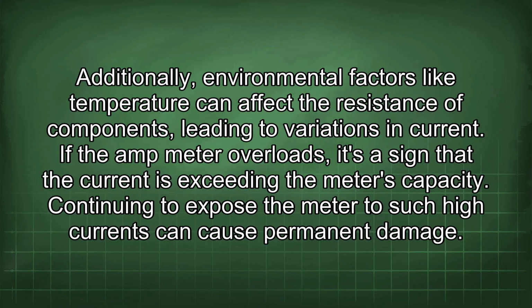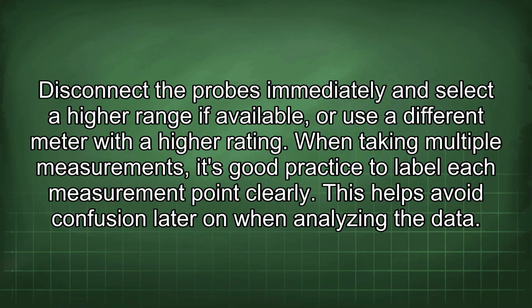If the amp meter overloads, it's a sign that the current is exceeding the meter's capacity. Continuing to expose the meter to such high currents can cause permanent damage. Disconnect the probes immediately and select a higher range if available, or use a different meter with a higher rating. When taking multiple measurements, it's good practice to label each measurement point clearly. This helps avoid confusion later on when analyzing the data.